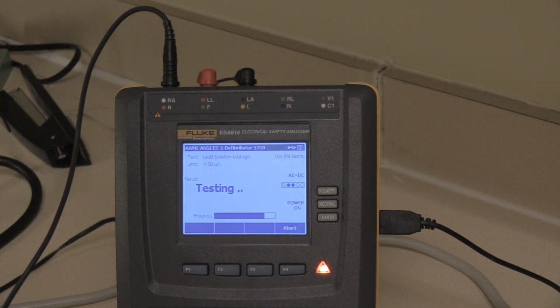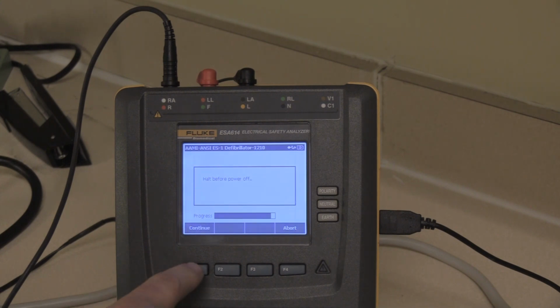This is all time that you could be entering your equipment records, preparing your sticker to place on the unit, making any notes. Here's another instruction to power the defibrillator off. We've powered off our defibrillator and we're going to continue with the test. And our test sequence is now passed.